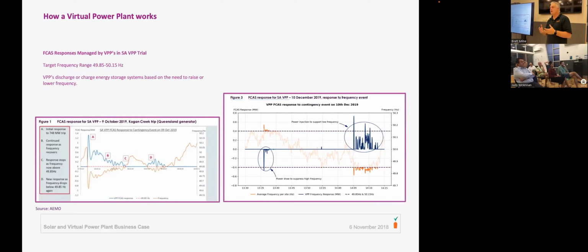If you have too much load being put into the grid, you'll get frequency spikes, and the batteries are used by virtual power plants to offset those frequency spikes. So when the frequency hits, say 49.85 and drops, the battery will then dispatch or charge depending on what it's trying to do. If it's trying to raise the frequency, it will dispatch. If it's trying to drop it, it will charge the battery. As it does those actions in the marketplace or in the grid, it brings frequency back into harmony, and then we avoid blackouts.